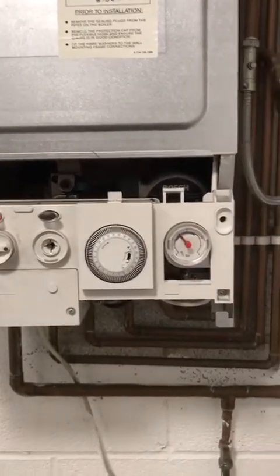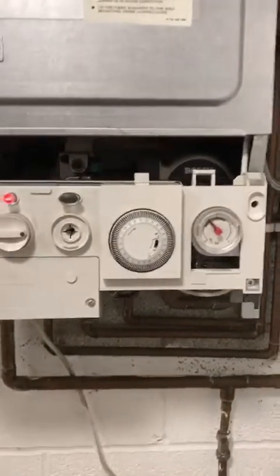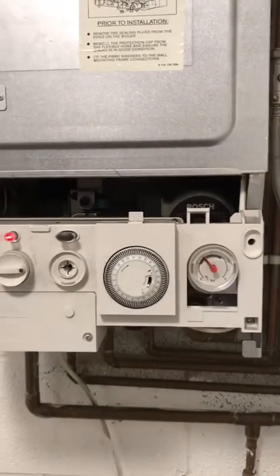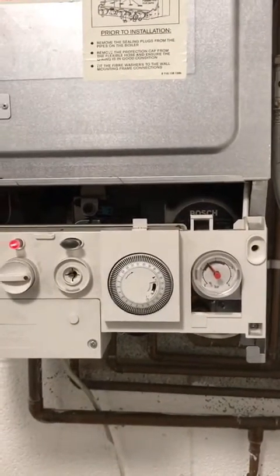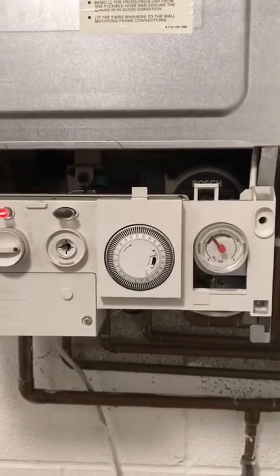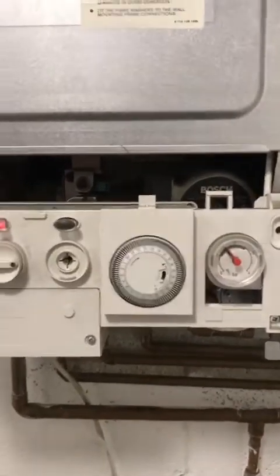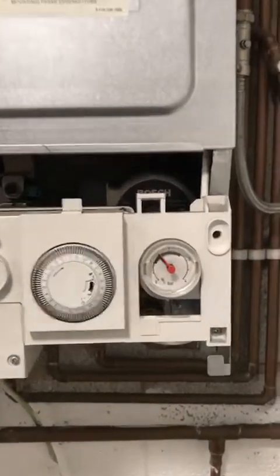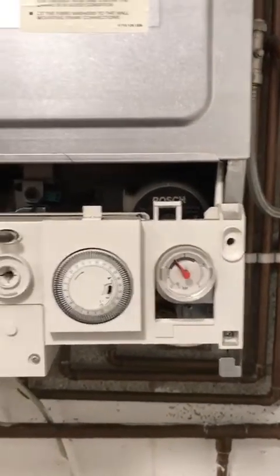When I got here, straight away I drained the boiler, checked the expansion vessel — which was flat — pumped it up to one bar, filled the boiler back up. Now I'm just running through its paces. So far the pressure is stable at 1.5 bar.